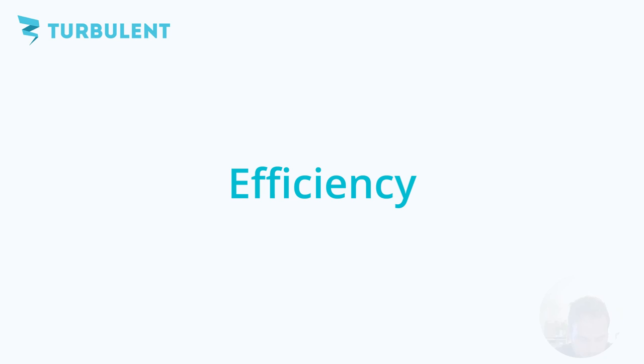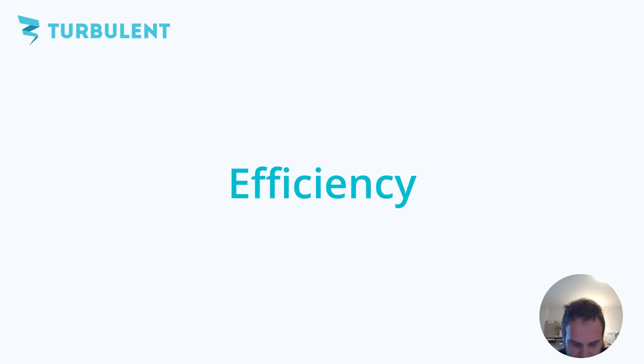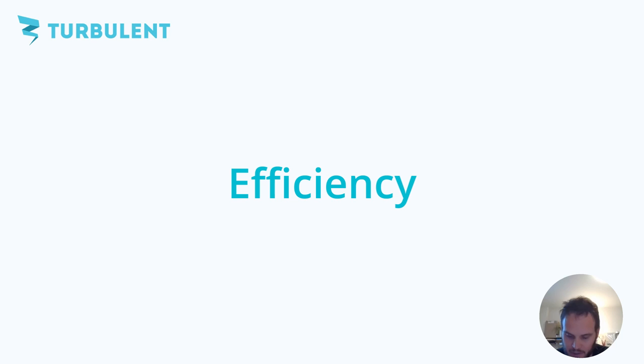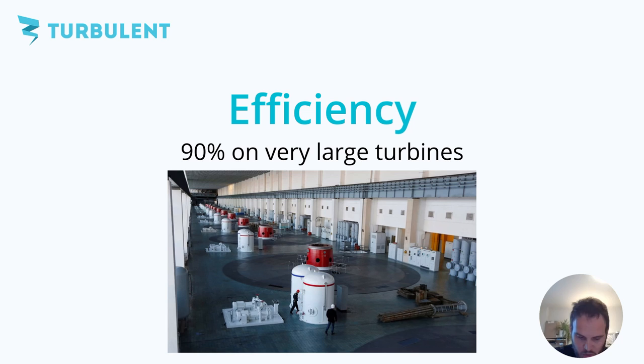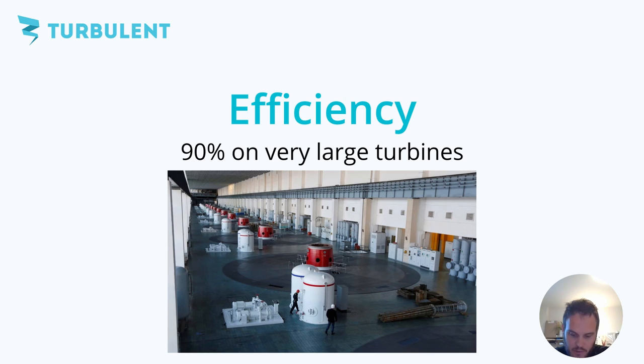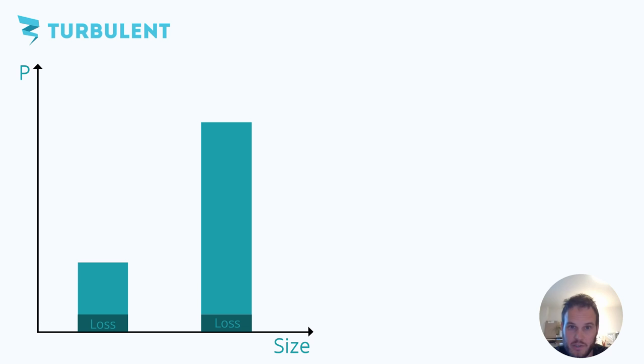At this moment it's a good time to say something about an extra factor of the formula that I haven't talked about yet and that's efficiency. Now when reading about hydropower you'll notice a lot of numbers are going around for this after all hydropower is quite an old industry and right now you might have seen numbers like 90 or higher for the efficiencies of the hydropower turbine. Now this is the case with very large turbines. Imagine a turbine as large as a room or even your house. With these kind of turbines they are fully optimized and they are fully customized to the site and except for that also the leakage losses and the friction losses etc will be relatively smaller in relation to the power that the turbine is producing. The losses that you have due to friction or leaks become proportionally larger for smaller turbines than with these kind of big turbines.